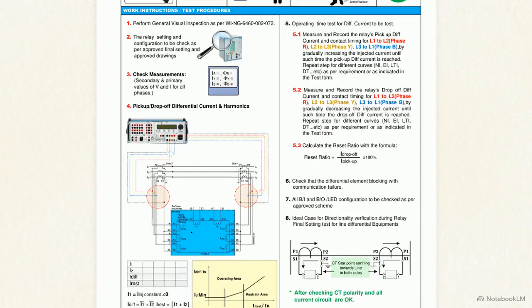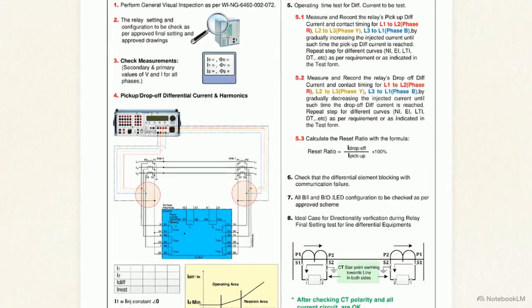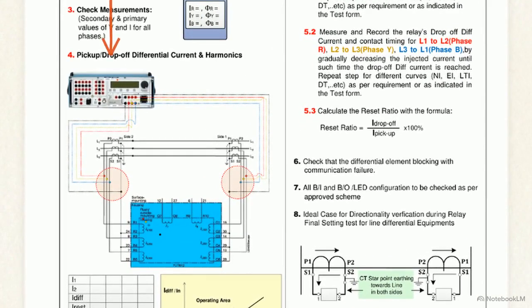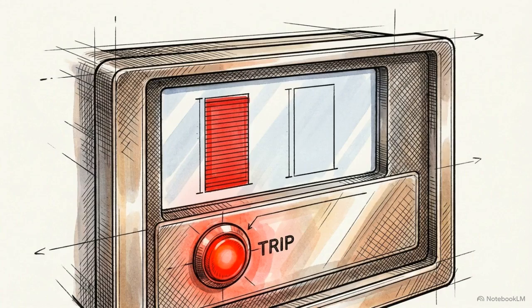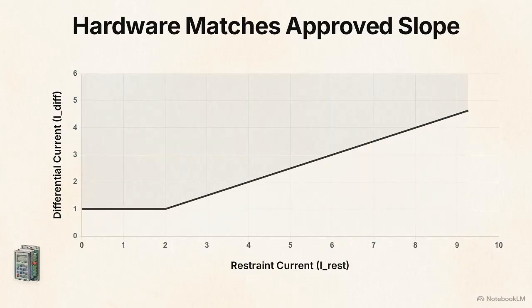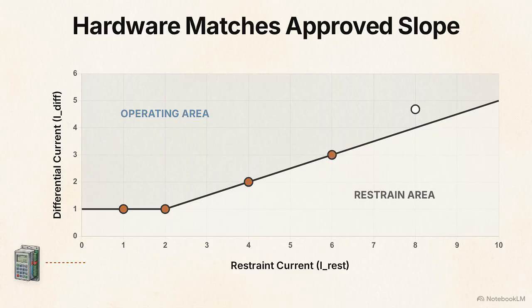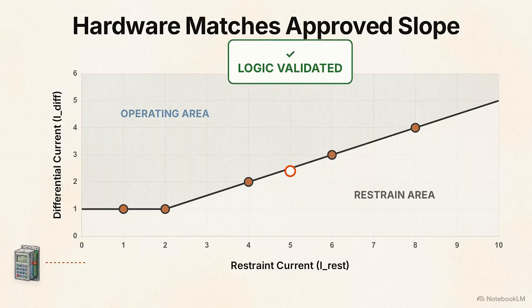This commissioning schematic for line and cable differential shows the testing setup. Technicians use the secondary test set to inject current into just one side of the simulated zone. This creates an imbalance to locate the precise pickup point where the relay identifies a fault and issues a trip command. To pass, the measured pickup and dropout characteristics must map perfectly onto the approved slope diagram, validating exact resetting ratios for different curve profiles.